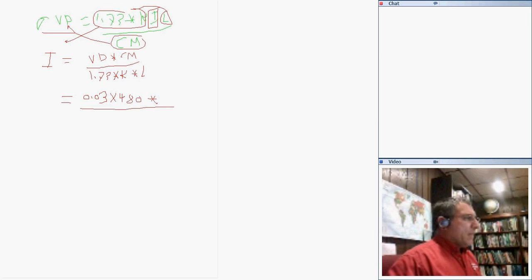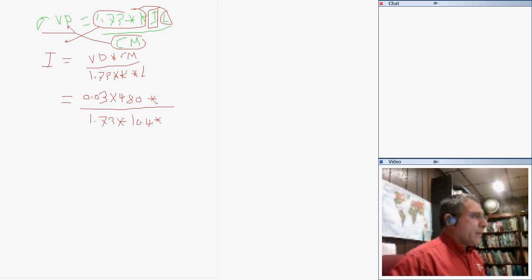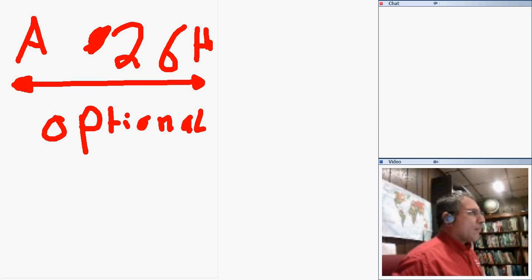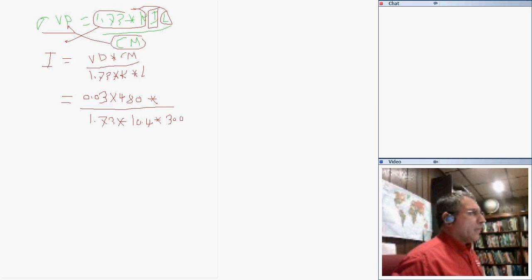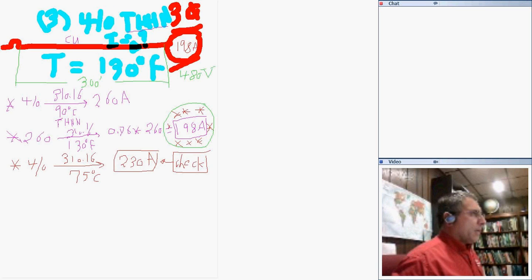We'll get back to the circular mil. Going back down to 1.73 times K. K is 10.4 based on the book that we have. It is 300 feet one way. The last piece is the circular mil for 4/0. My equation was 4/0. Yes, it was a 4/0.